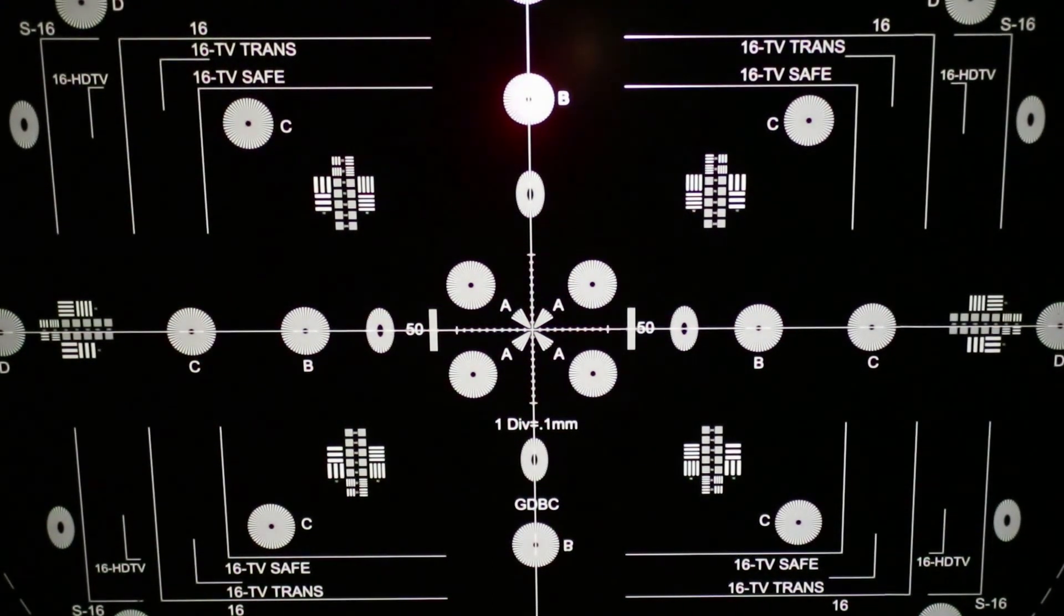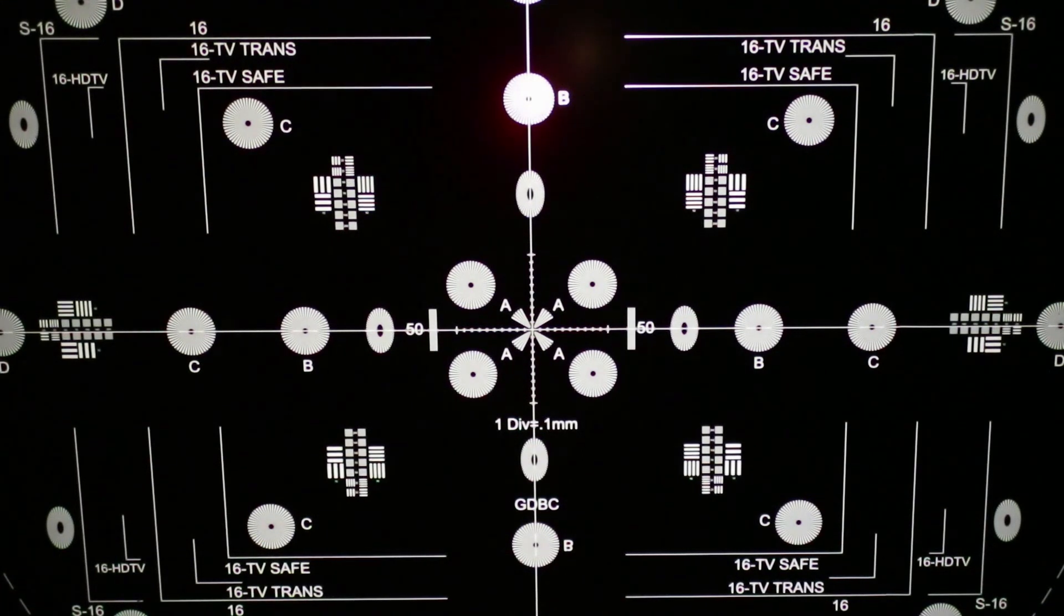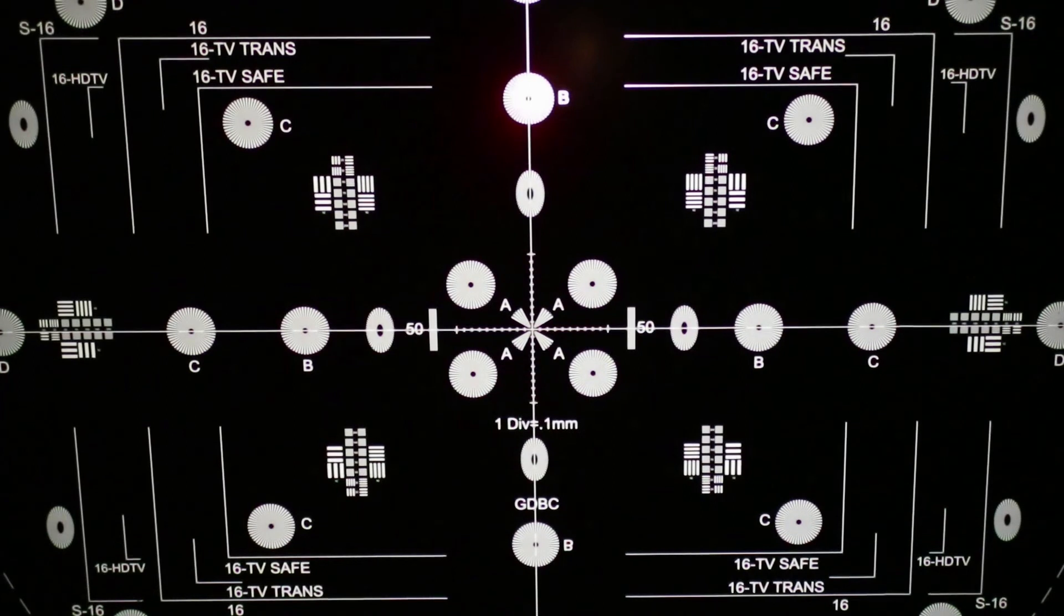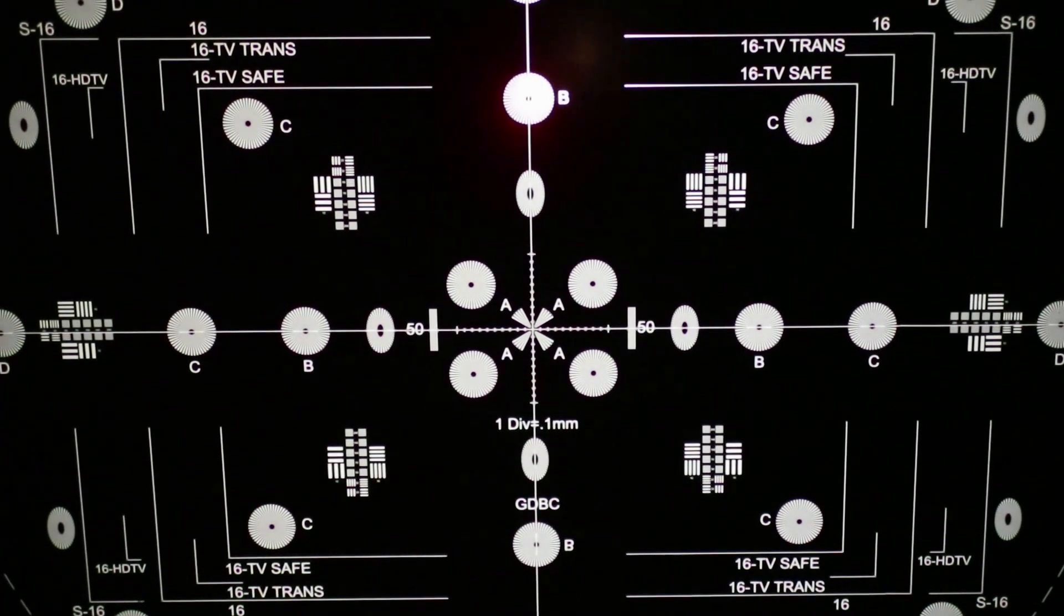Reverse projection allows the operator to easily evaluate multiple field points of a lens simultaneously. Reverse projection is often used to speed up the lens testing process in high-volume production.